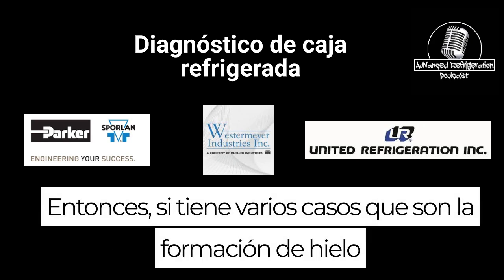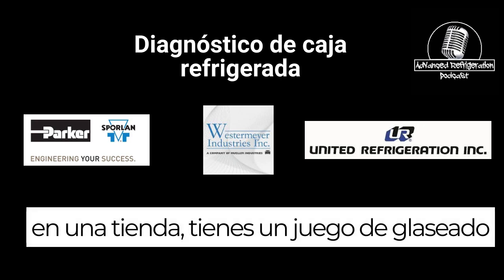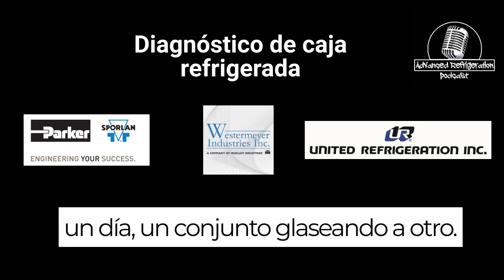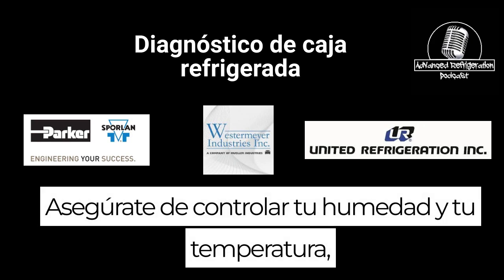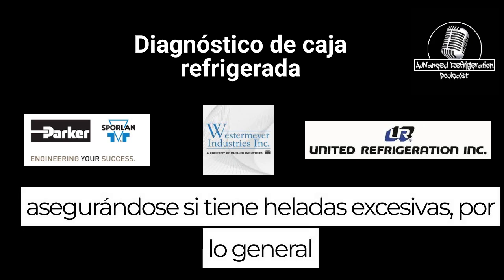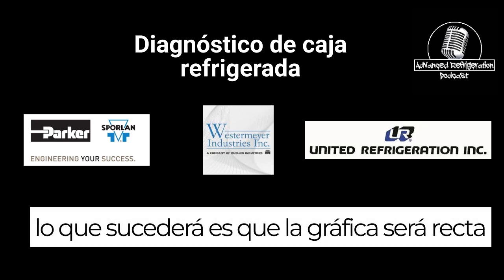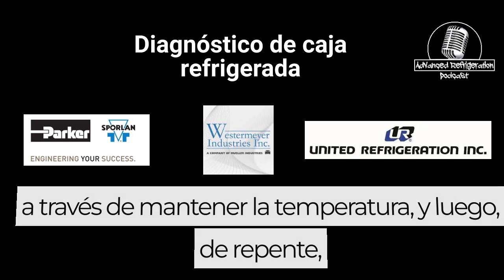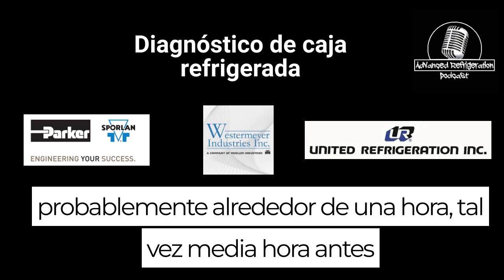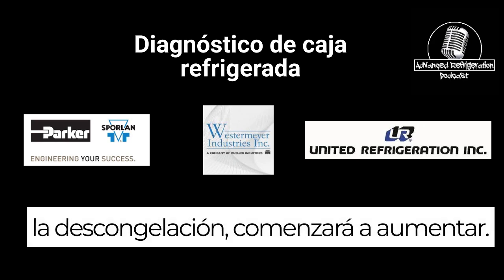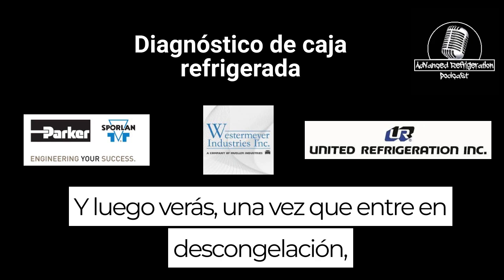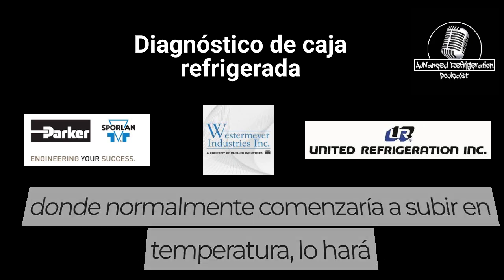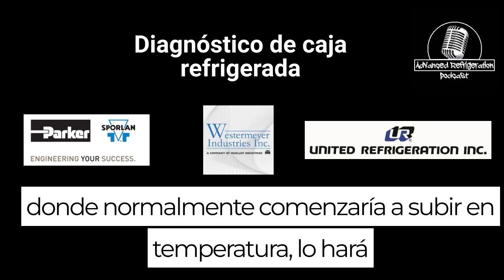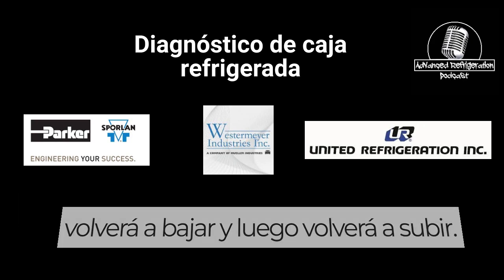So if you have multiple cases that are icing up at a store, one set icing up one day, another set another day, make sure you're checking your humidity and your temperature. If you do have excessive frost, usually what will happen is the graph will be straight across, holding temp. And then all of a sudden, about an hour, maybe half an hour before the defrost, it'll start spiking up.